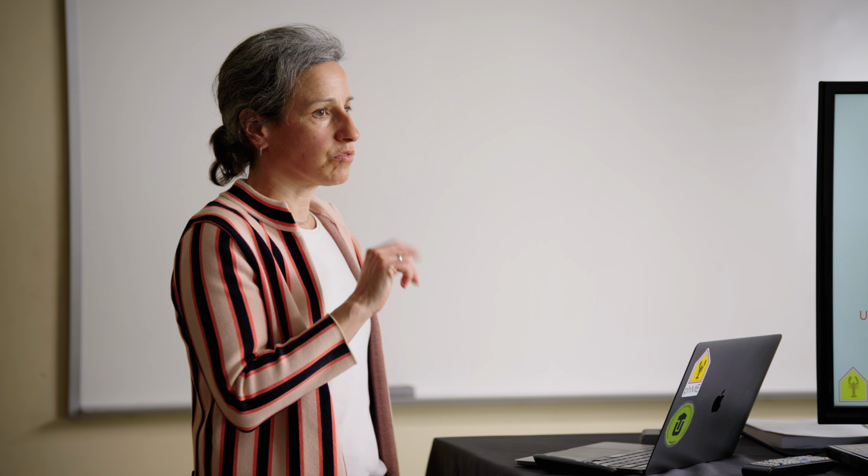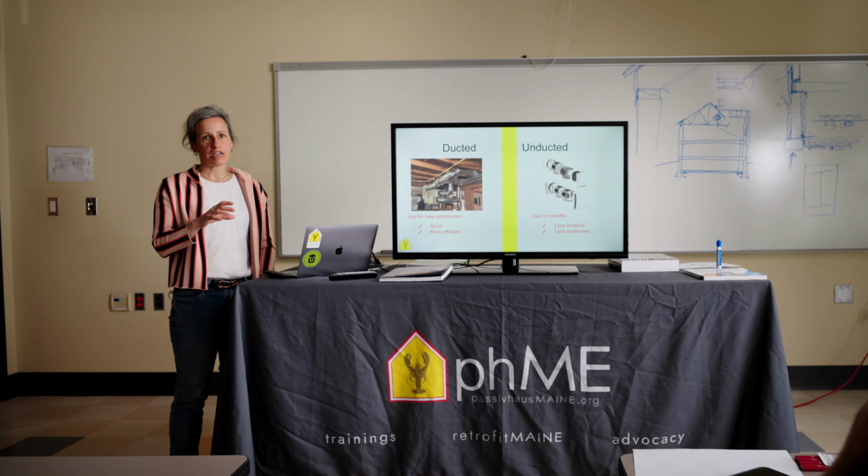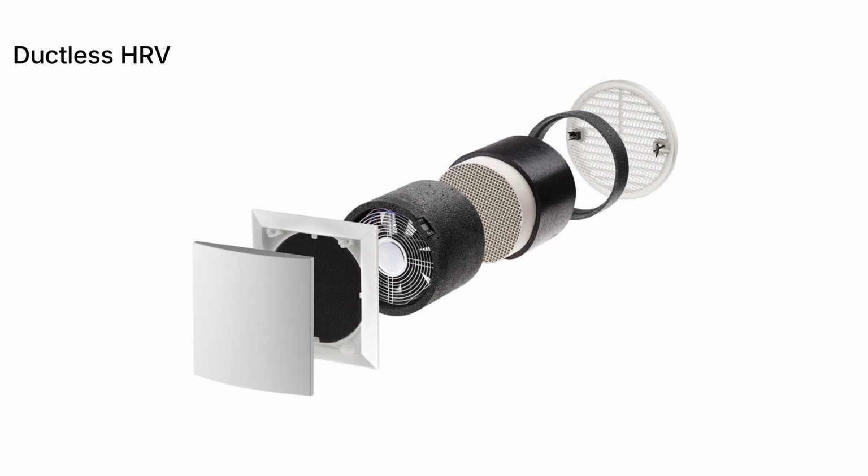99% of the time it's done through a ducted system, so there's one unit and then it runs with noodles throughout the building. You do want to use rigid ductwork most of the time. For the most part, it is true that you want hard ducts. Soft ducts create too much resistance in them. There are 2 different companies that make these cool little cylinders that go directly into the wall. They're really great for renovations when you can't get all those noodles run through the building.